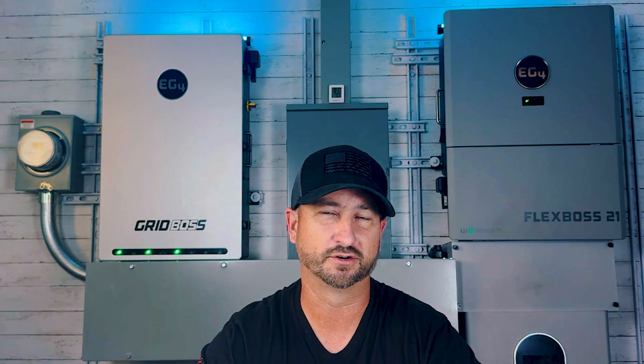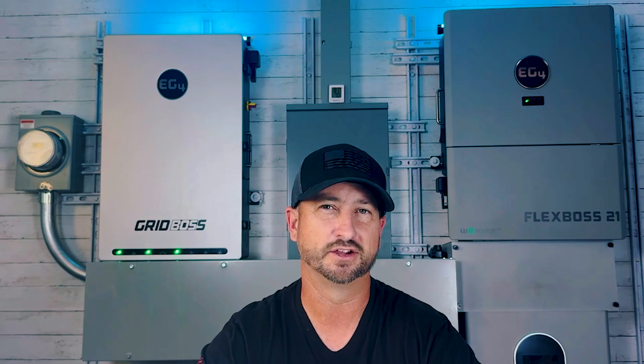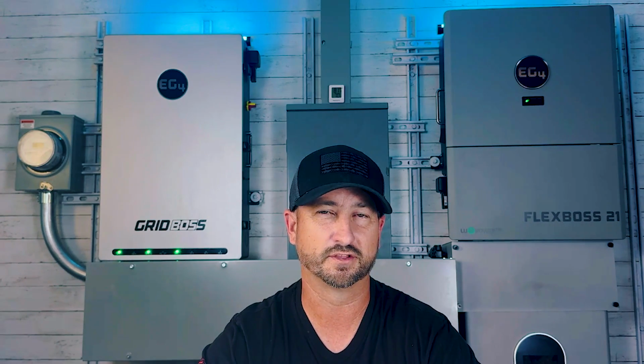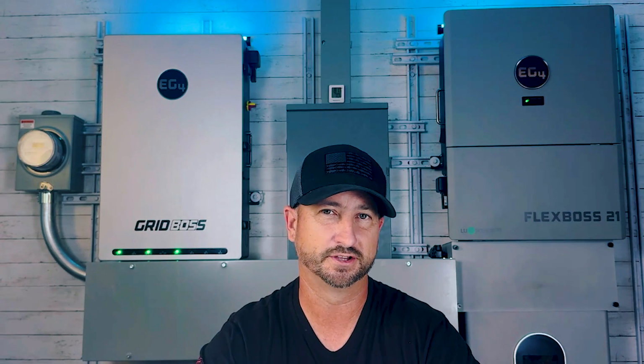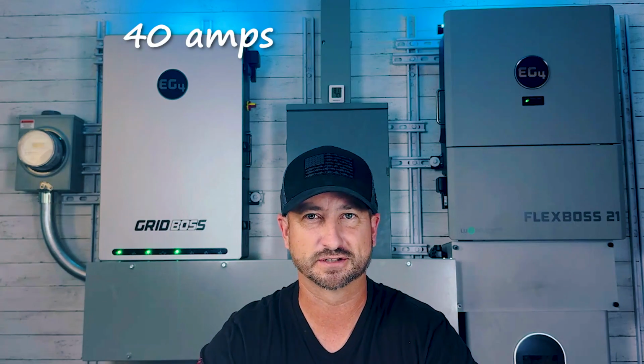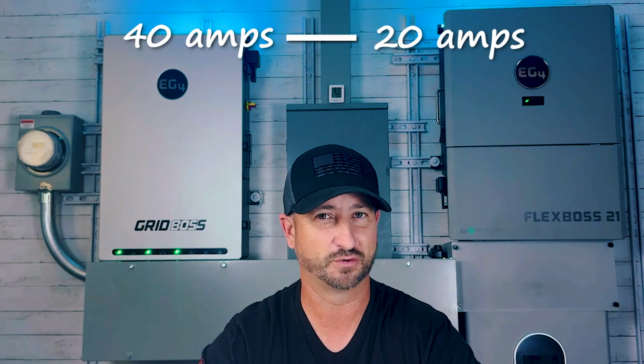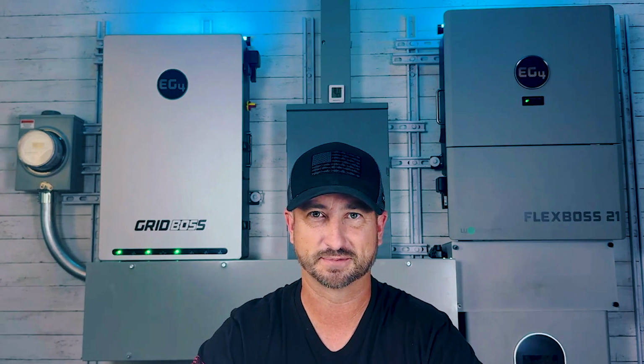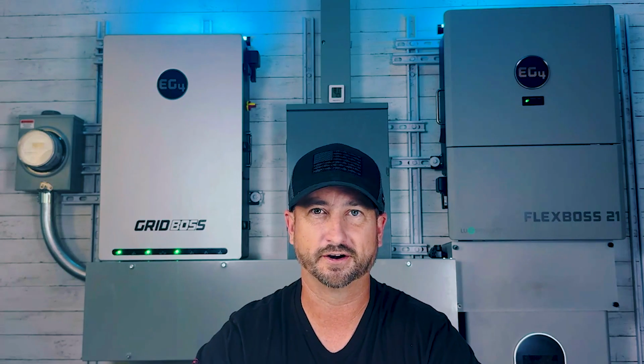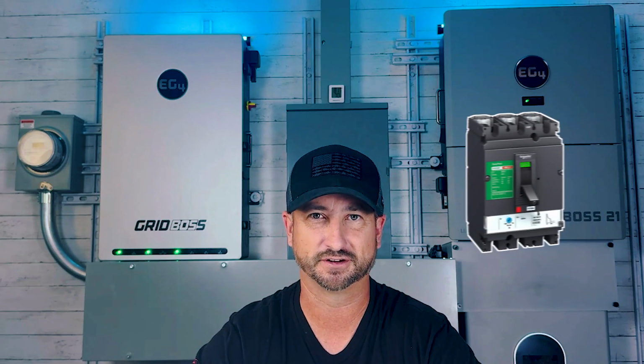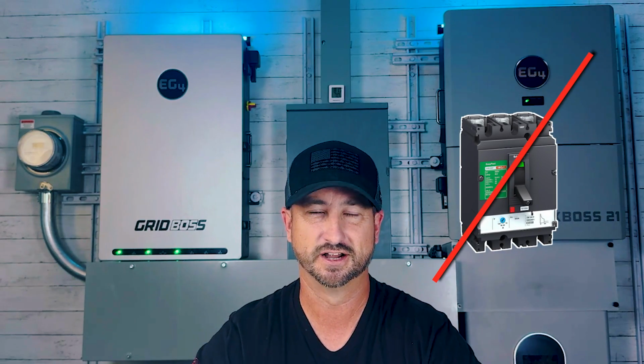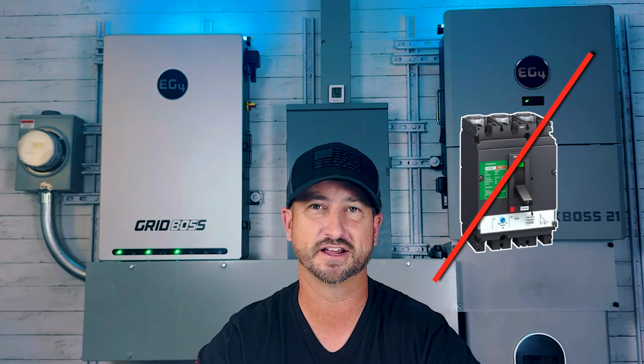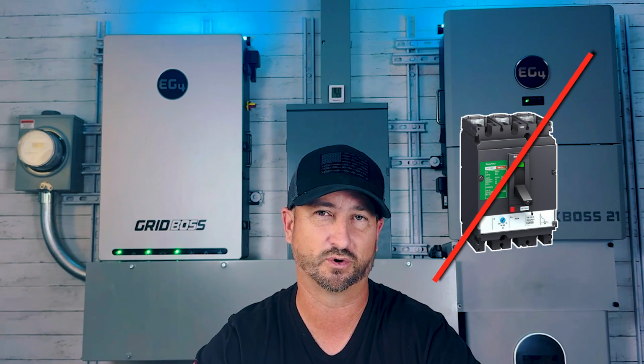If you're installing your own circuit breakers and fuses, make sure they're rated for the right amount for the size wire you're putting into them. It doesn't matter if you put in a 50 amp breaker when your wire is only rated for 20 amps. If you push 40 amps through that wire, you're going to melt it and it'll turn into a fire, and that breaker's not even going to trip. So the breaker is essentially useless. You have to make sure the breaker is sized for the wire and amps you're using.